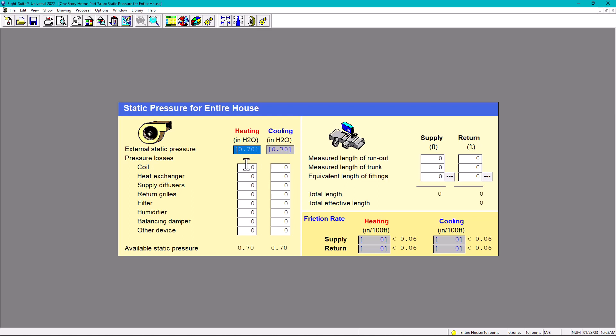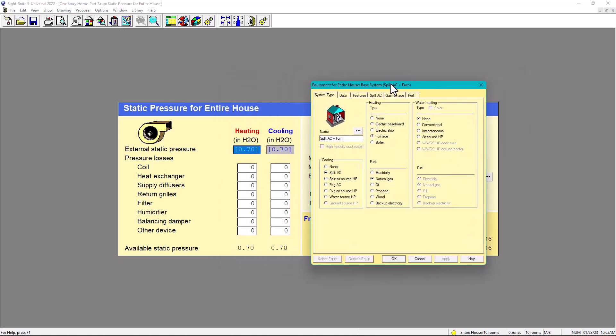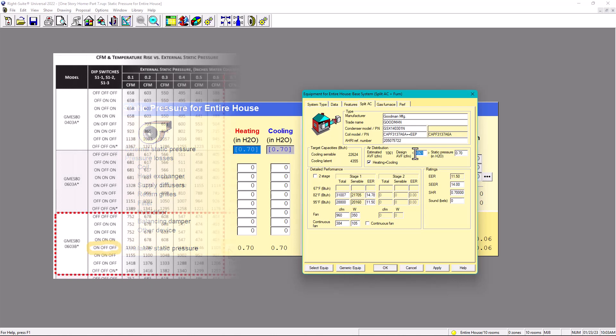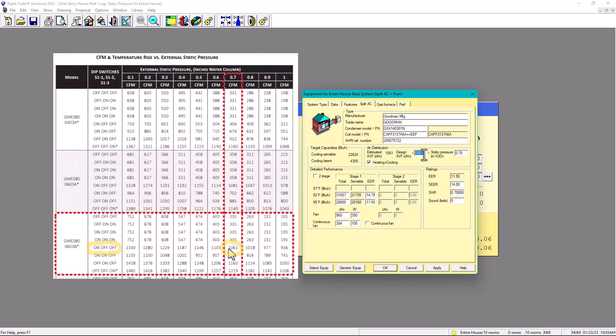This is a very interesting topic. What is remaining from our static pressure after the losses? And what are we providing with the fan? With the fan, we're providing 0.7 external static pressure at the equipment design CFM. As you remember, if we go here in the equipment, we had already selected the system - a split AC - with 1,061 CFM, which is based on the manufacturer. CFM is married with static pressure, so you talk about CFM at what static pressure. The static pressure is 0.70.